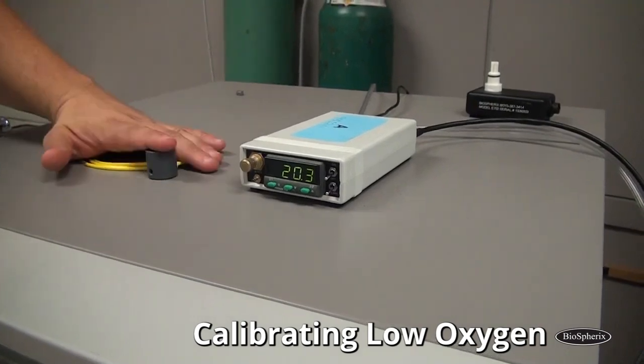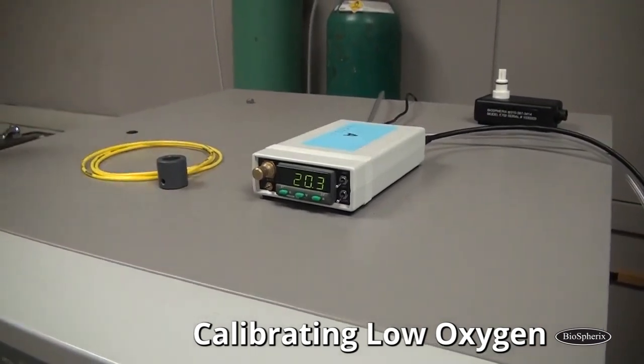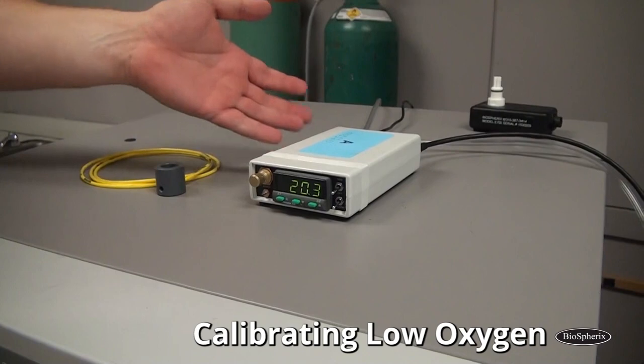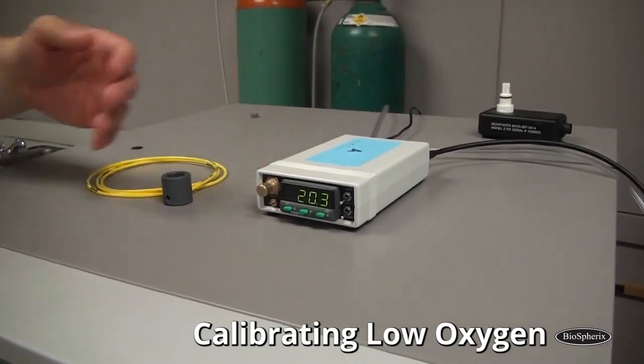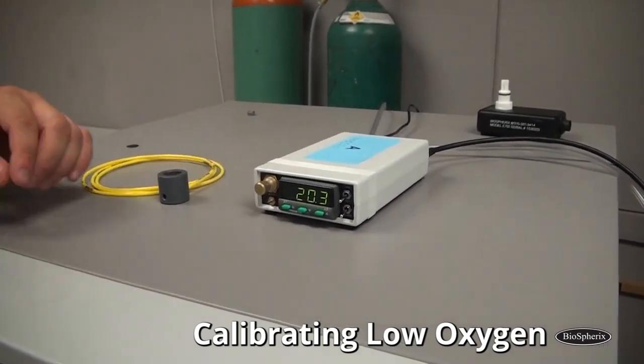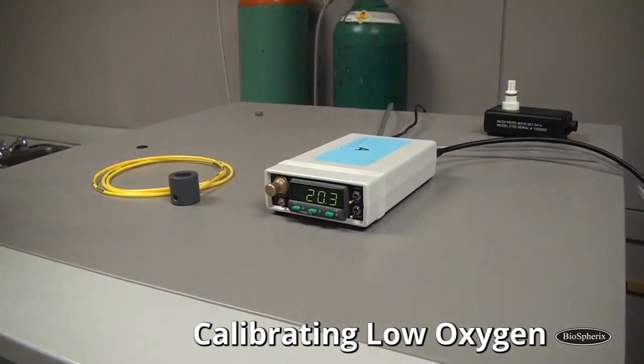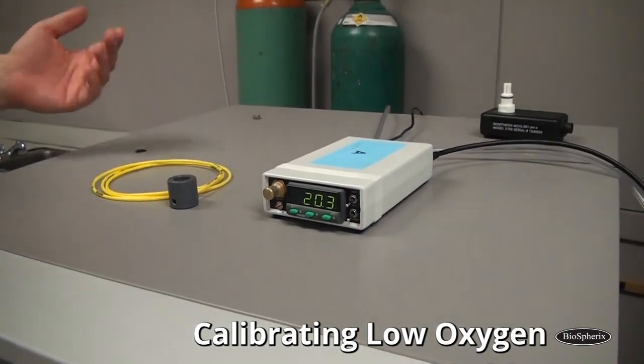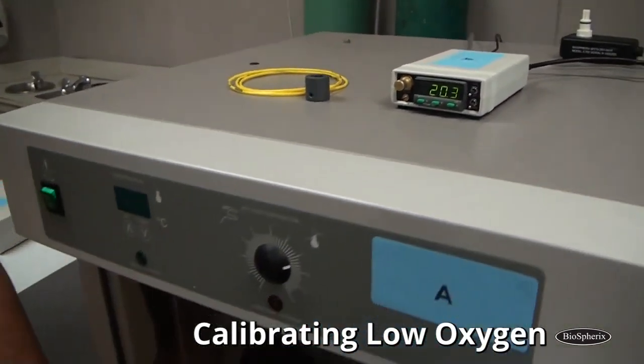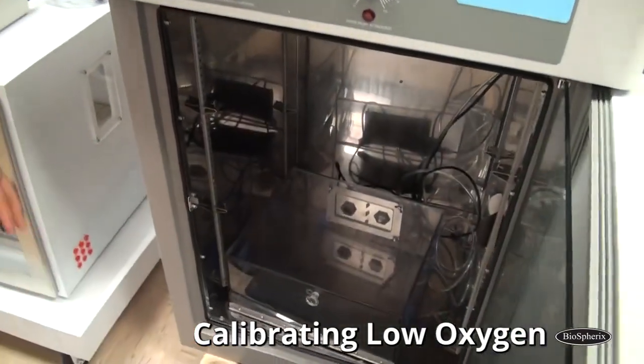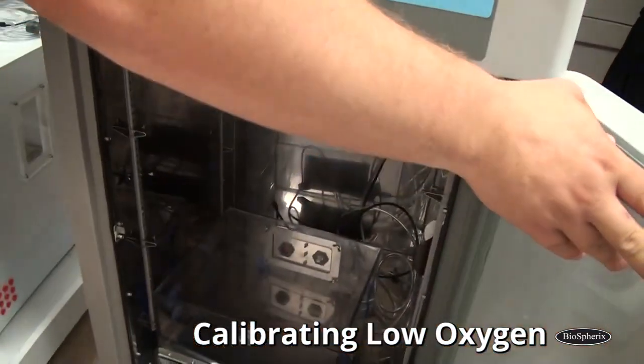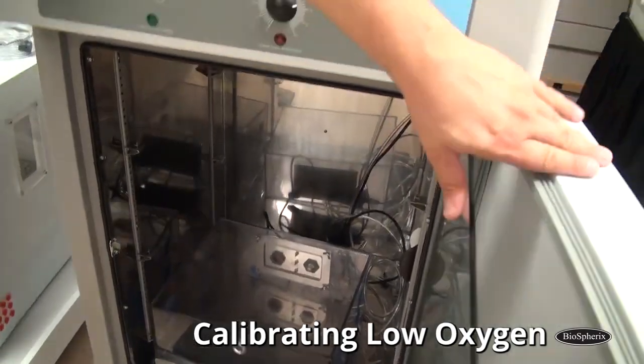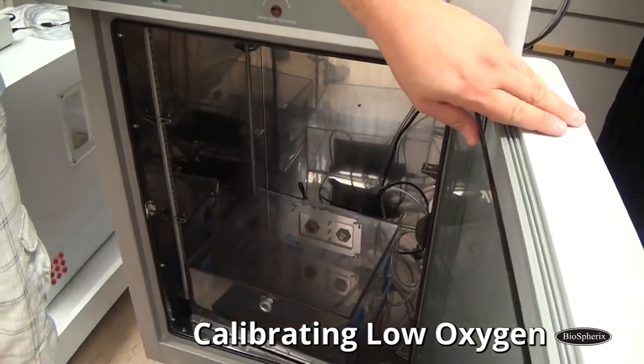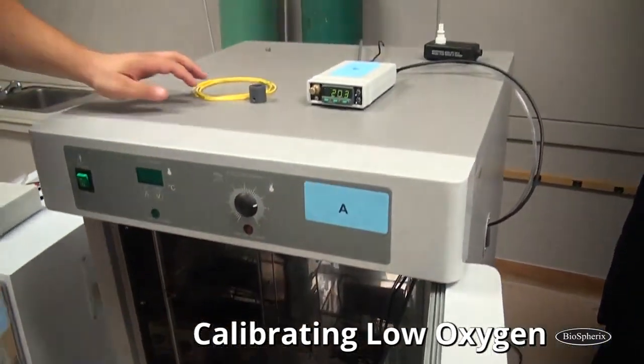So I have my calibration chamber, and I know I have nitrogen gas, which will be our low calibration. We call it the zero calibration. So I need a high. So the high is going to be room air, because if I open this door up, it's just exposed to 20.8. So that's my second known standard. So I'm going to do this calibration right now. I'm all set to go.